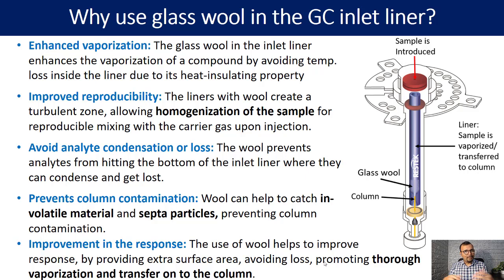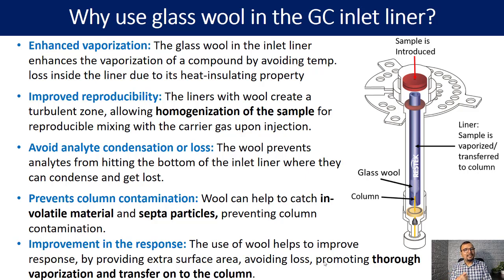There are many advantages of using the glass wool in the liner. However, one has to also think about replacing the glass wool on a frequent basis, because the glass wool gets contaminated due to the sample matrix and involatile particles. The replacement of the glass wool is very essential, and one has to also think of cleaning the liners on a frequent basis. I hope this video helps to understand why one has to consider the glass wool. Thank you so much.